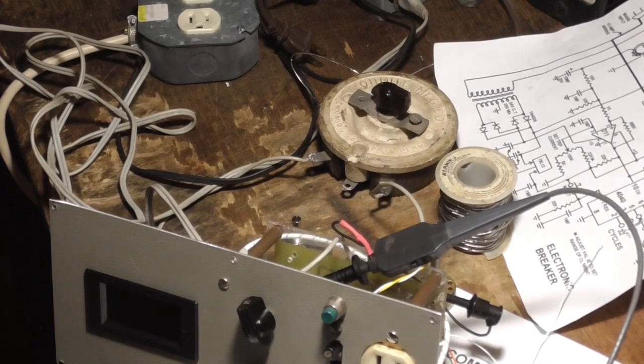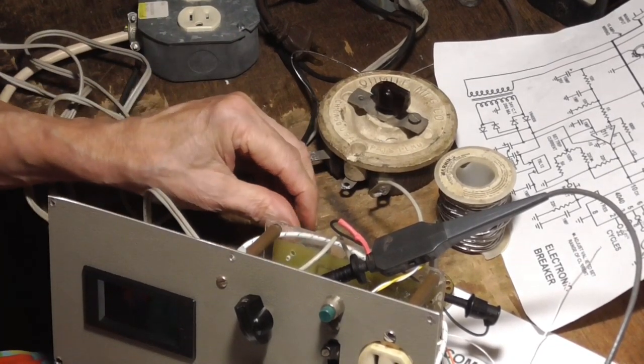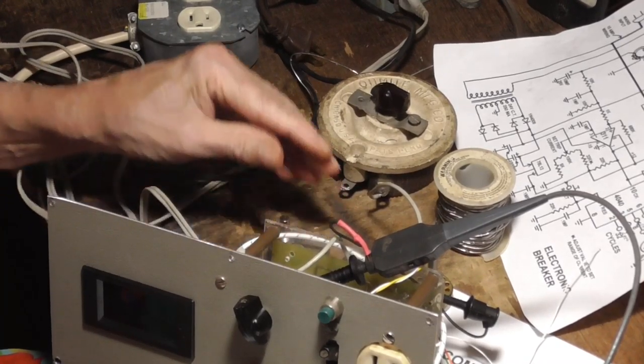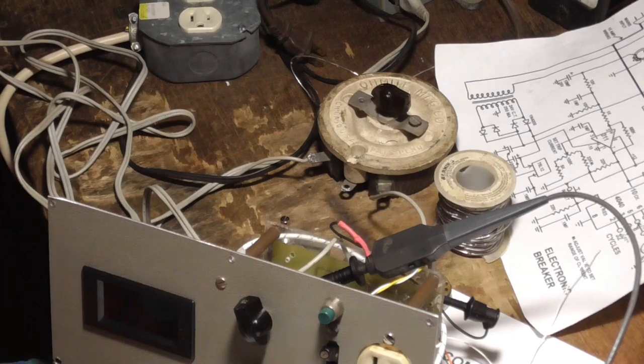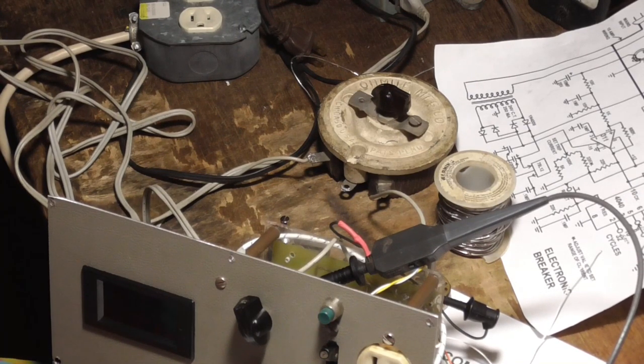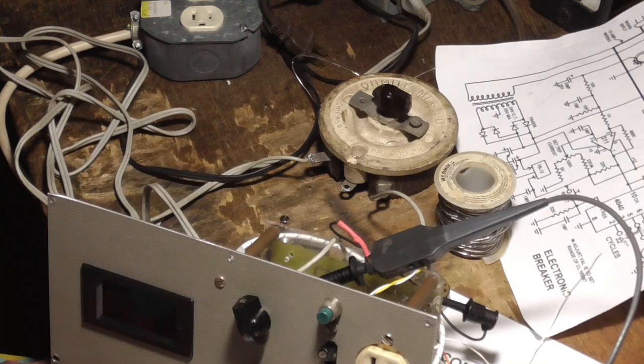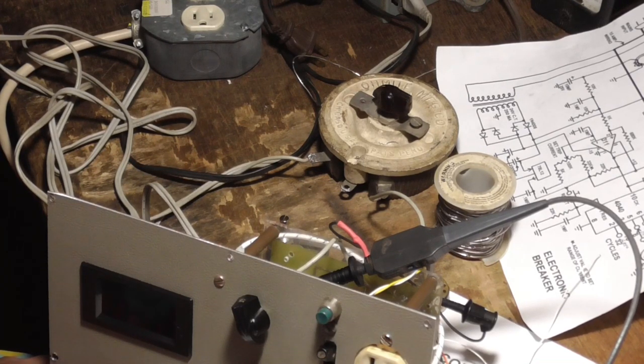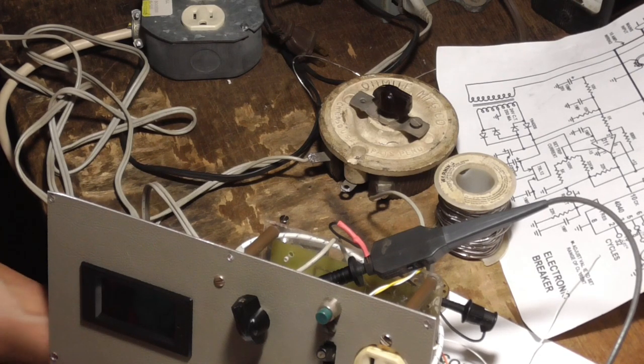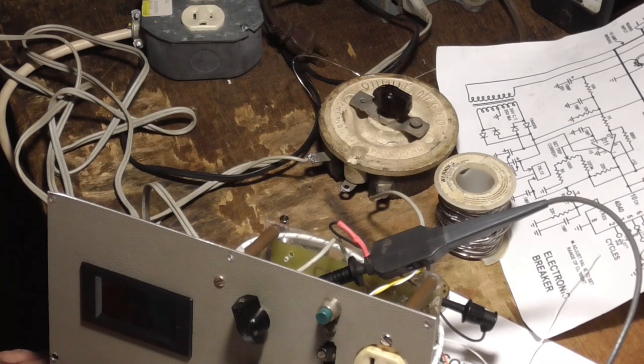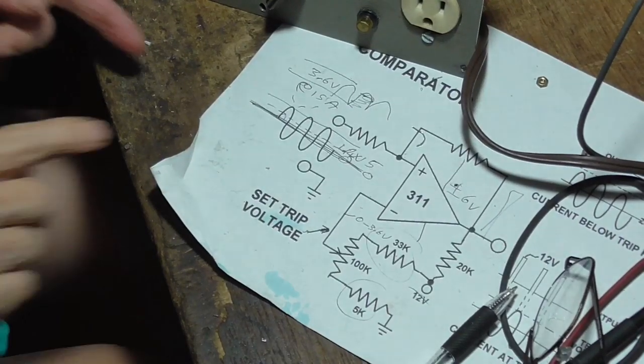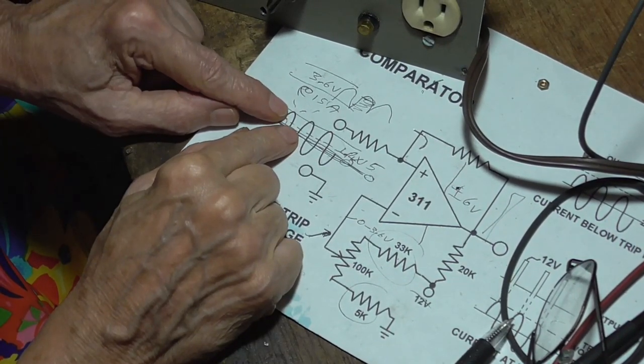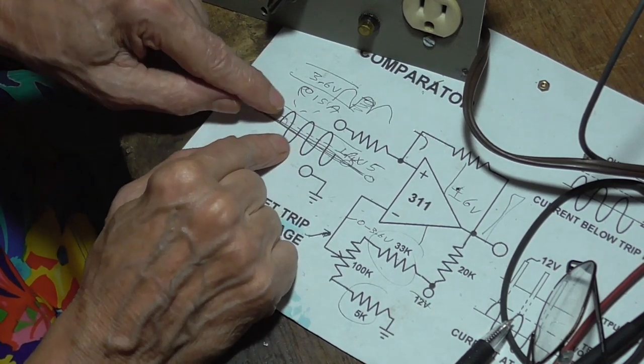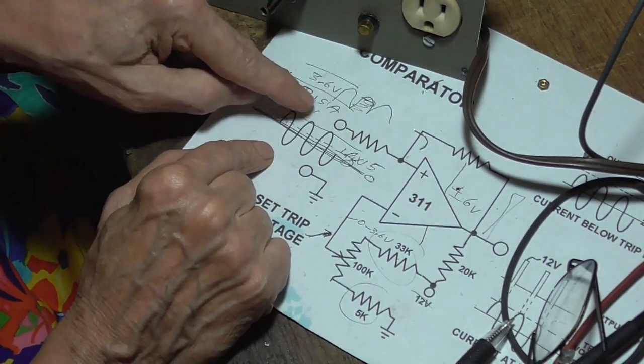Now what we're going to do is set this up for the correct current. We've got to adjust the two resistors that are feeding power to the trip voltage potentiometer. The first thing we do is look at the output of the sensing circuit at given currents, and see how many volts peak we get on the comparator.